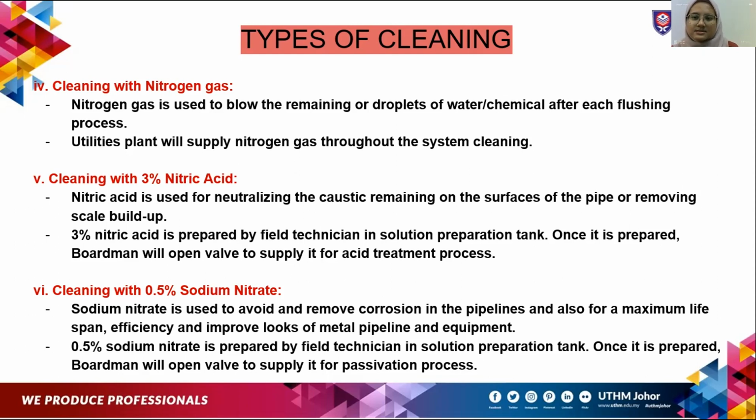The last type of chemical cleaning is cleaning with 0.5% sodium nitrate. Sodium nitrate is used to avoid and remove corrosion in the pipelines, and also for maximum lifespan, efficiency, and improved looks of metal pipeline and equipment. So here, 0.5% sodium nitrate is prepared by the technician in the solution preparation tank. Once it is prepared, Boardman will open the valve to supply it for the passivation process.